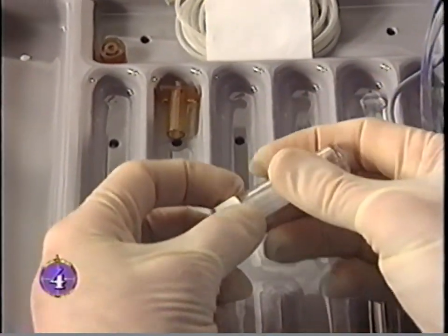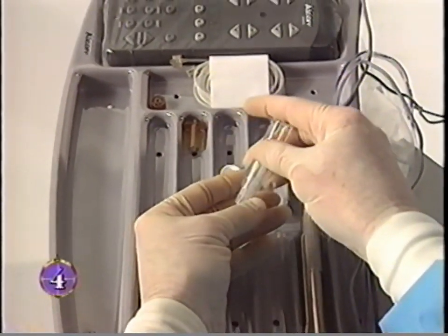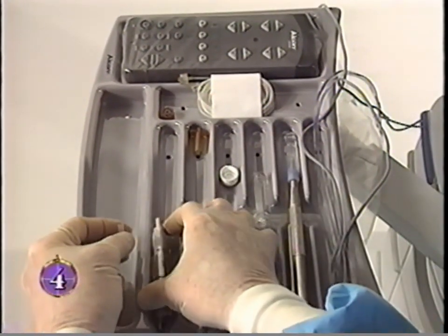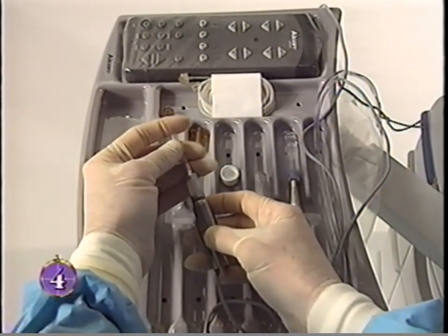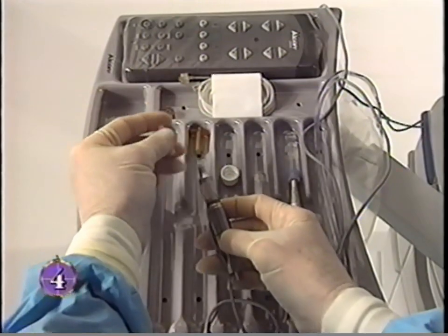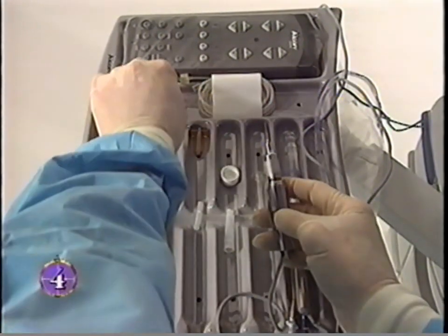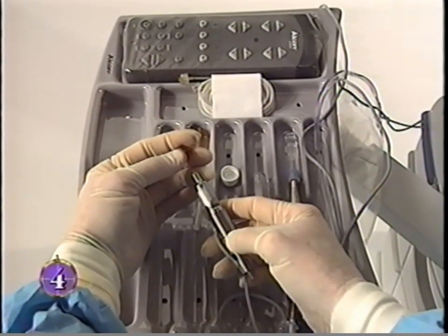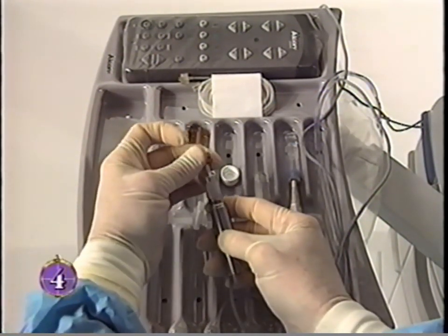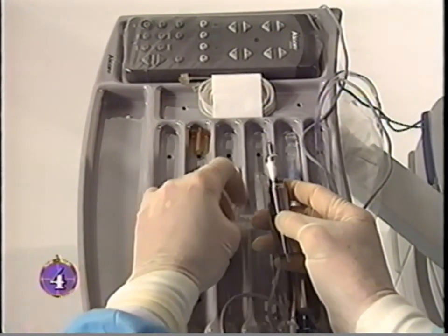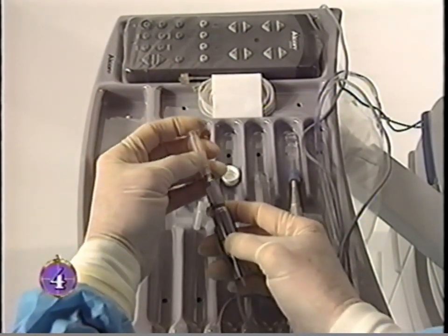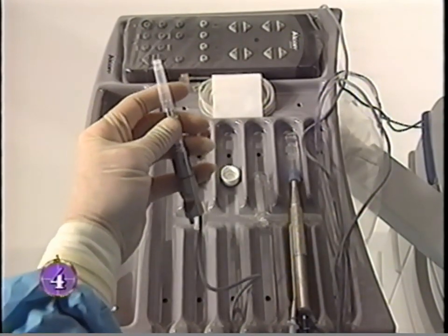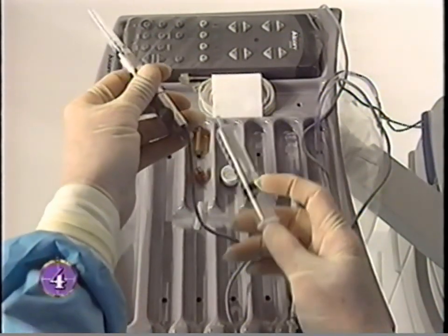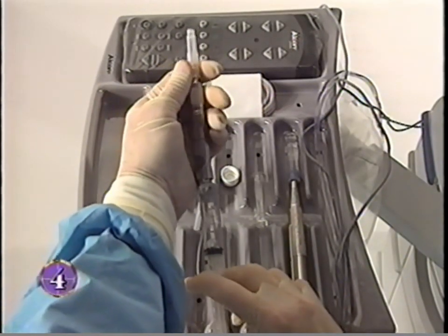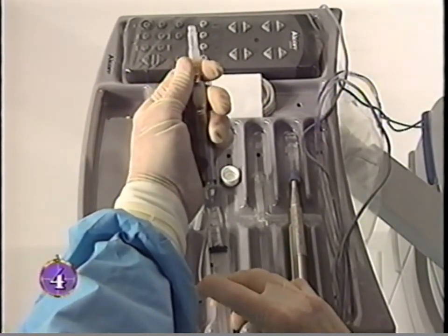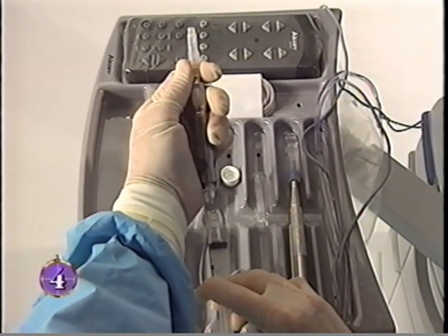Remove the tip and thread it onto the handpiece using the silicone tube as a holder until the tip is tightened. Remove the silicone tube and use the round side of the wrench to tighten the tip securely. Do not over-tighten it. Install the vented tuning chamber over the tip on the handpiece. Hold the handpiece vertically, tip up, and using the syringe, gently flush the female luer with 10 cc of BSS solution. The vented test chamber should be full.